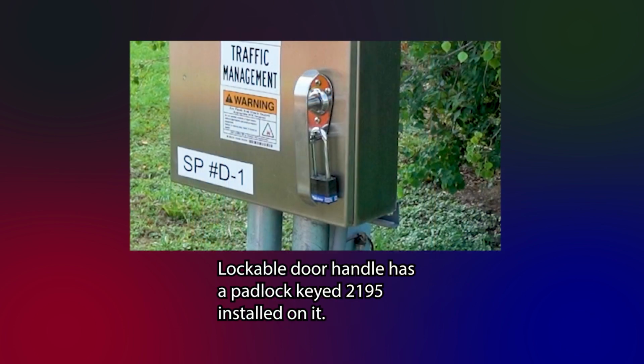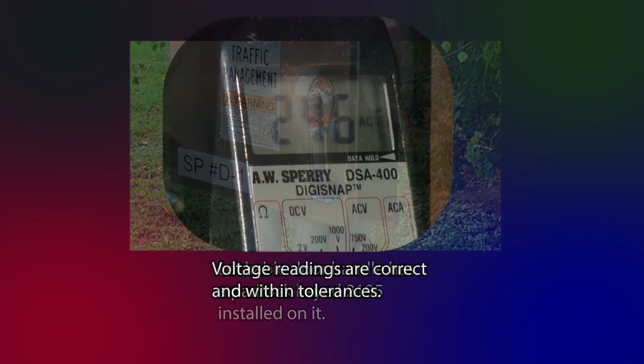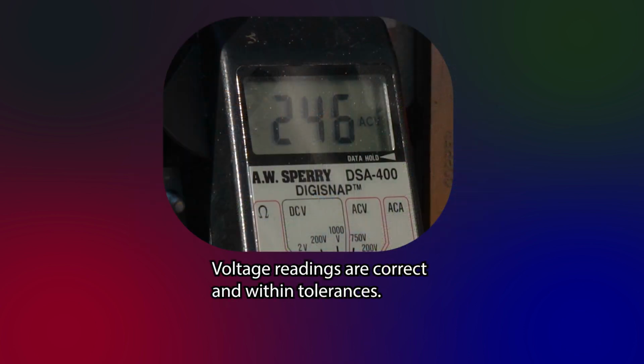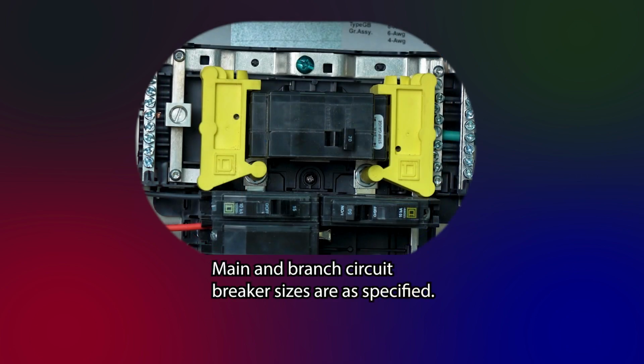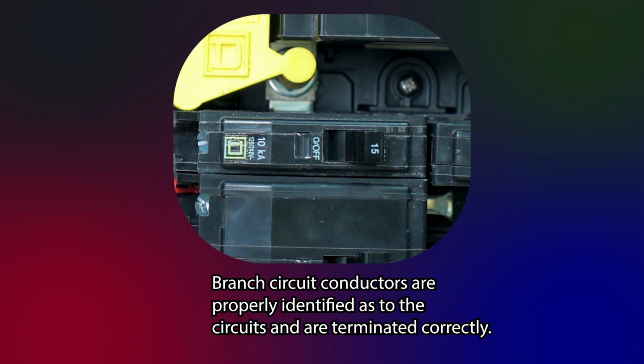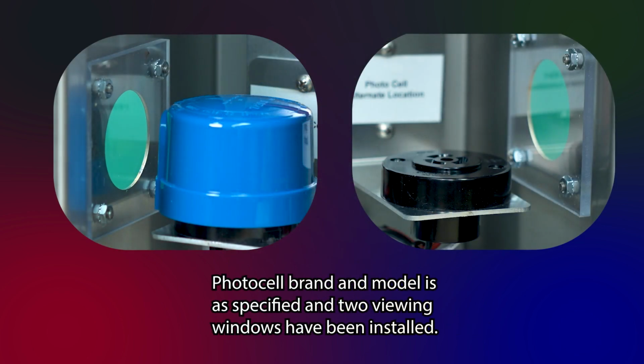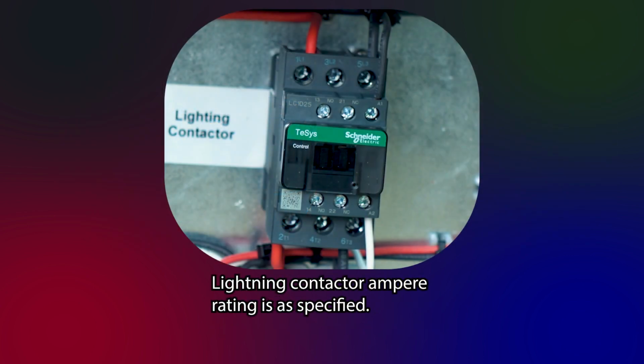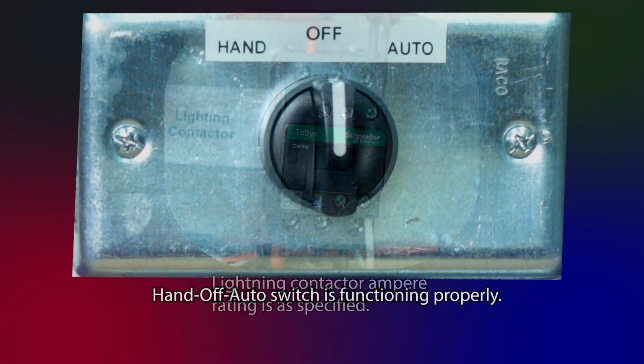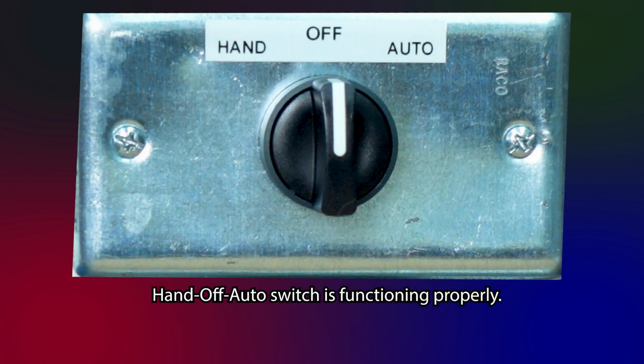Lockable door handle has a padlock keyed 2195 installed on it. Voltage readings are correct and within tolerances. Main and branch circuit breaker sizes are as specified. Branch circuit conductors are properly identified as to the circuits and are terminated correctly. Photocell brand and model is as specified, and 2 viewing windows have been installed. Lighting contactor ampere rating is as specified. Hand-Off-Auto switch is functioning properly.